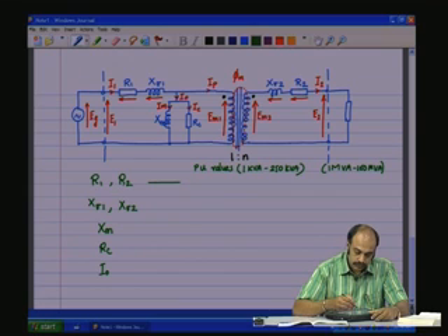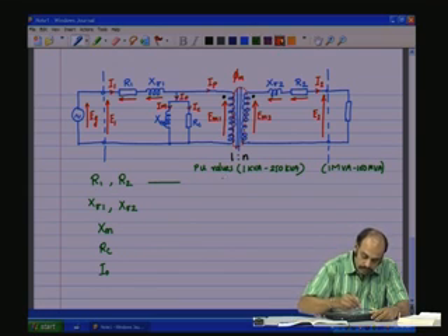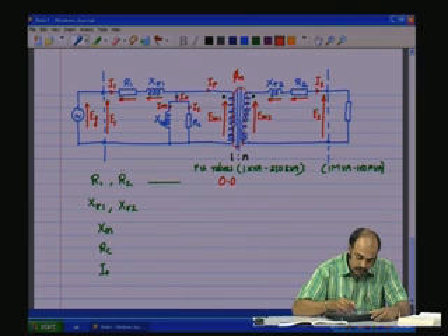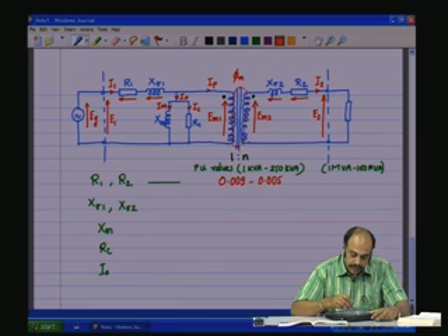So, for R1 and R2, the per unit values range from 0.009 to 0.005. That is, it is 0.009 at around 1 kVA, 0.005 at around 250 kVA, and one could do a linear interpolation for different other VAs in between. And these values vary from 0.005 to 0.002. Per unit values are dimensionless quantities. You see, actually the variation is not much, from 0.009 to 0.005 for 250 kVA variation, and for around 100 MVA variation also 0.005 to 0.002.